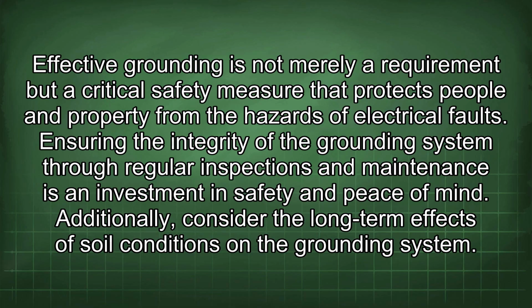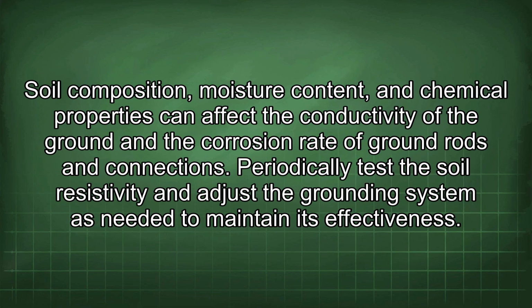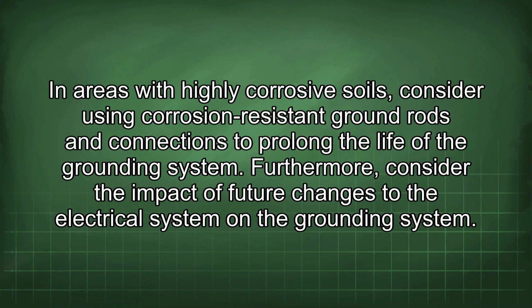Additionally, consider the long-term effects of soil conditions on the grounding system. Soil composition, moisture content, and chemical properties can affect the conductivity of the ground and the corrosion rate of ground rods and connections. Periodically test the soil resistivity and adjust the grounding system as needed to maintain its effectiveness. In areas with highly corrosive soils, consider using corrosion-resistant ground rods and connections to prolong the life of the grounding system.